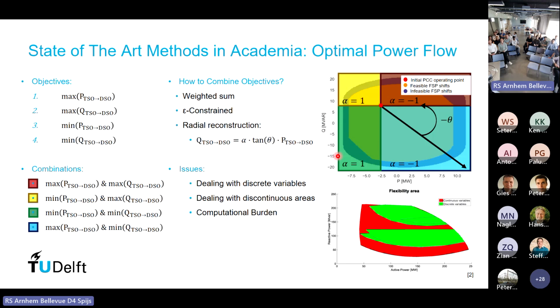Starting with the optimal power flow-based approach, this approach says that starting from this operating point, as shown previously, we have four main objectives: to maximize the active power from the TSO to the DSO, to maximize the reactive power from the TSO to the DSO, and to minimize those values as well. However, it's clear that the first and third, and the second and fourth, cannot be combined together because they are exact opposites.